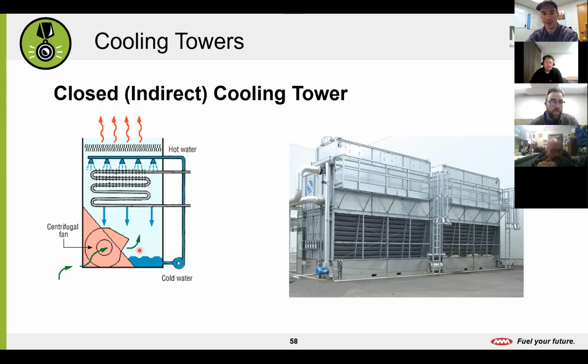You'll have water level sensors. You have a sump pump on these, where you don't on that open style cooling tower. So there's going to be some more components to them, but the maintenance costs would be less. You don't have to clean them nearly to the extent you do on the others. And you don't necessarily run into the same risks of pulling in all that outside junk into your pipes and clogging up your building. So I prefer them a lot more.